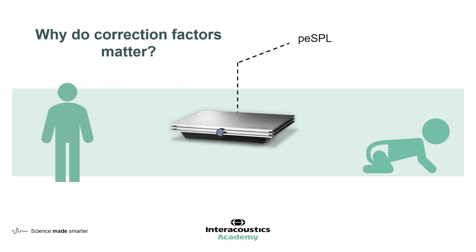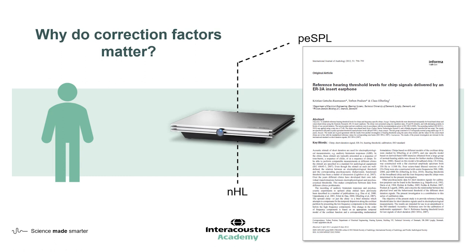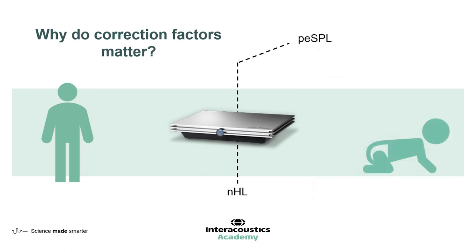Evoked potential systems should be calibrated using the correct electrical peak equivalent sound pressure level calibration of the transducer. The RETSPL values are then applied in order to convert the physical peSPL into nHL, which is a hearing sensitivity-related scale. RETSPL values are provided by the ISO standard 389-6. The CE chirp family of stimulus, which is found on the Eclipse, is not yet included in this standard, but there are independent studies which have been published on the CE chirp family which detail the RETSPL values and this conversion.